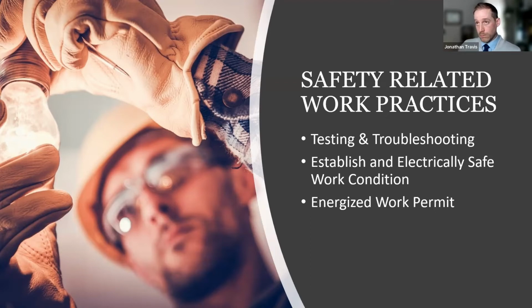Now, this may change per jurisdiction, but let's just use NFPA 70E as the base point here. If it's below 750 volts, at that point, you're good. You've established an electrically safe work condition. You can actually remove your PPE and continue to work in that panel or whatever you're doing. If it's above 750 volts, there's one more step, which is applying temporary protective grounds. So that's another piece that, if that's something you need to understand how to do, you need to be trained and understand how to do it. And you probably should have a procedure in your program about installing temporary protective grounds.